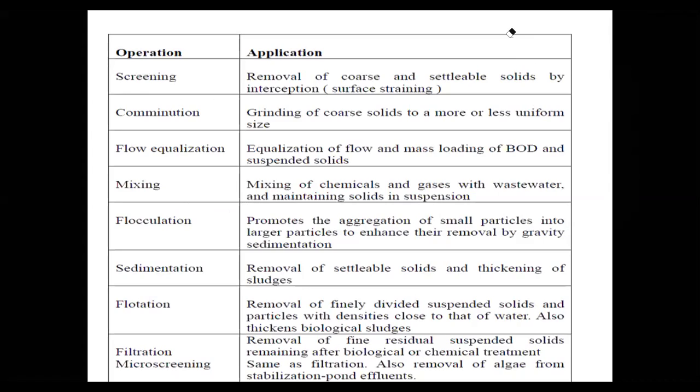Screening is used for the removal of coarse and settleable solids by interception. Then comminution: the grinding of coarse solids to a more or less uniform size. Flow equalization: equalization of flow and mass loading of BOD and suspended solids. This part you write down. Actually, for sketching purposes, I should draw, and I will give you that figure in the next lecture. I think I have not added it in this lecture.